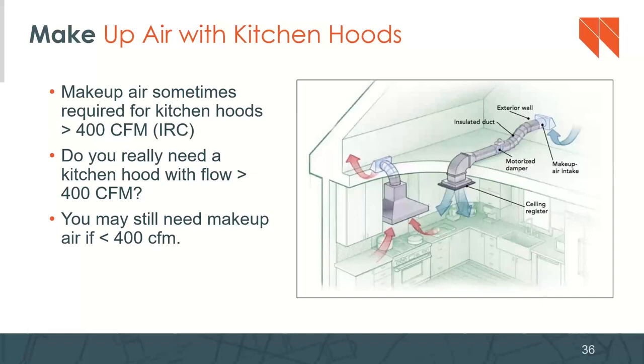In terms of considerations for range hoods that vent these particulates outside, there can be the need for makeup air sometimes. Within the residential code, anything over 400 CFM, so if your kitchen hood that's vented to the outside is rated to move more than 400 CFM of air, you're going to need to do a makeup air system with it. And what we're finding in some homes with a very tight enclosure is that even if you have a kitchen hood that is less than 400 CFM, you still might need makeup air.